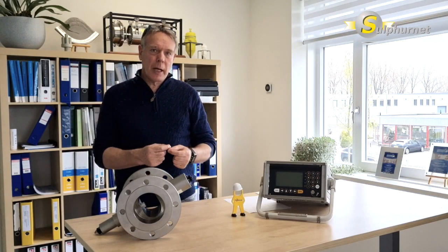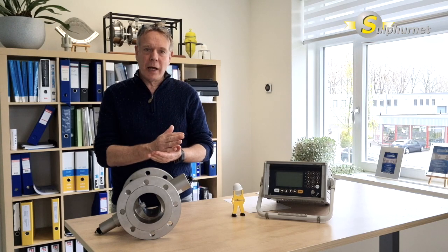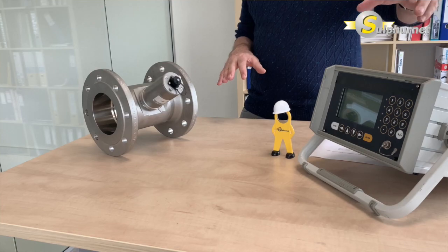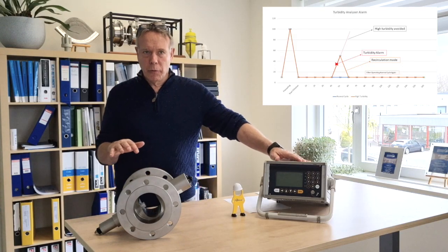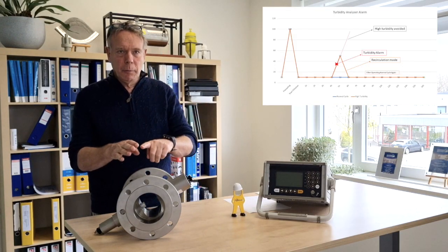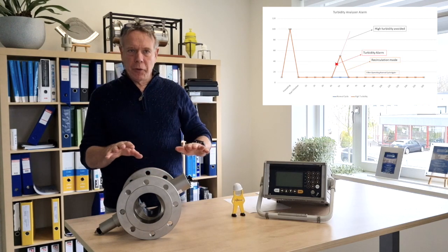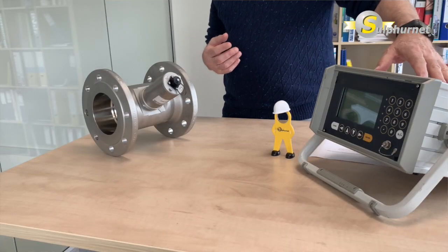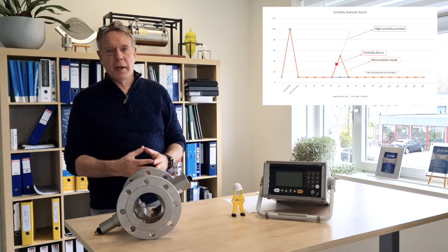The best way to set up the system is to measure the turbidity level and install a threshold in your system, so that you say we have 10 ppm, that is the level that we want to measure. As long as this cell measures less than 10 ppm, nothing will happen. When 10 ppm is exceeded, you get a signal, and based on the signal you can take an action.